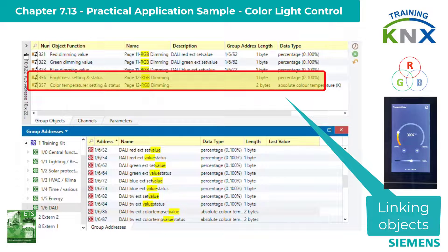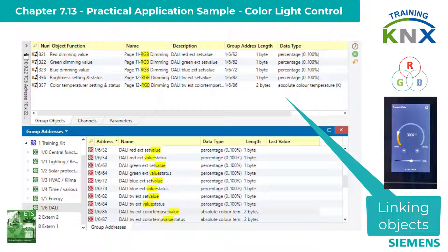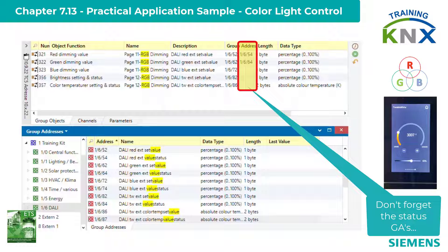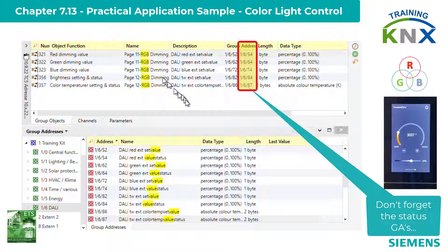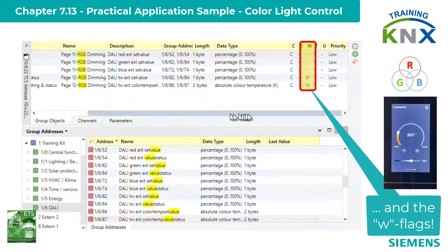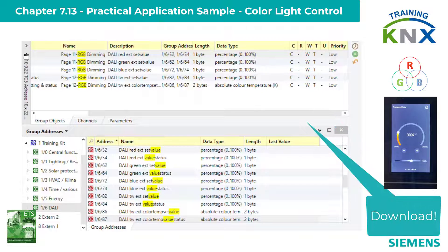On page 12, the dimming value and the absolute color temperature are linked. However, it is recommended to also set the respective status address behind the control addresses and also to activate the read flag. This ensures that the display of the control page always remains up to date, even when controlled via other inputs.